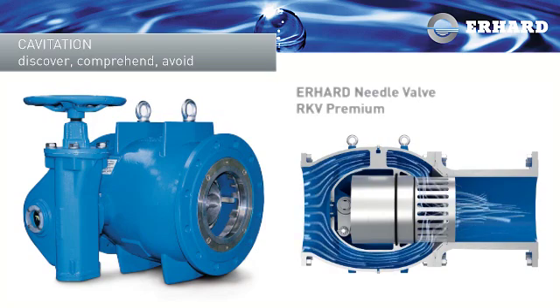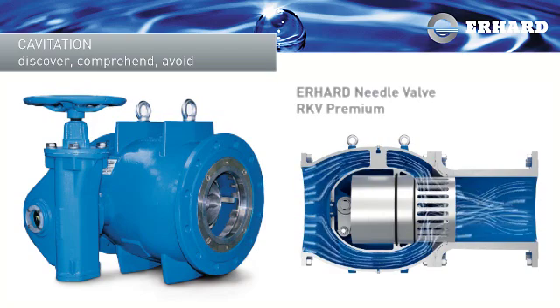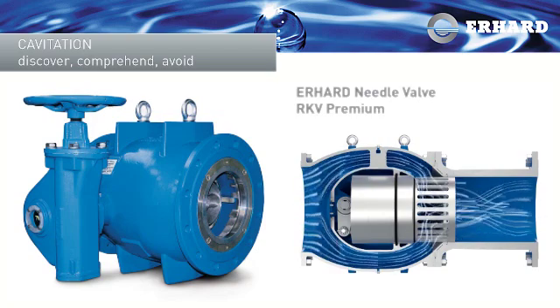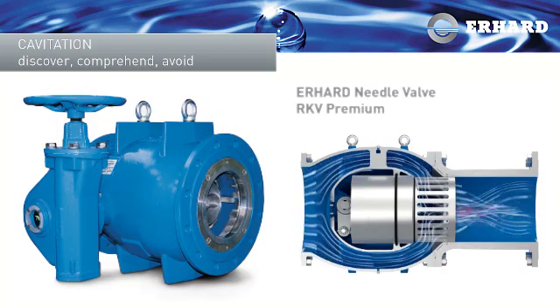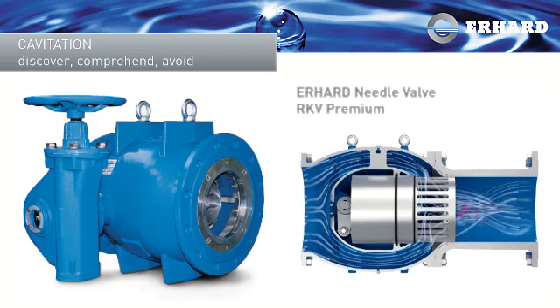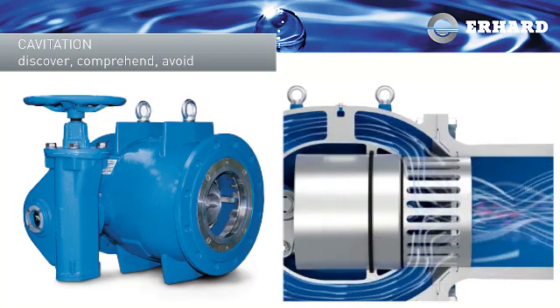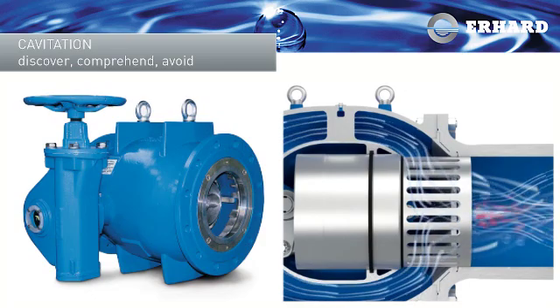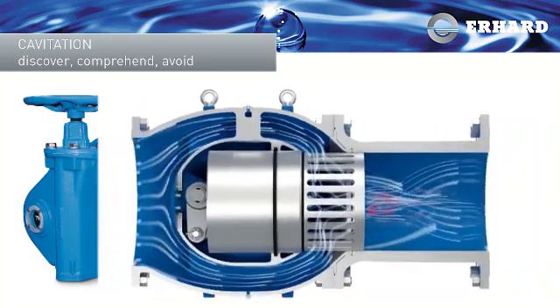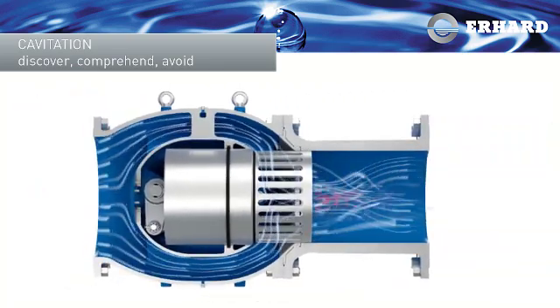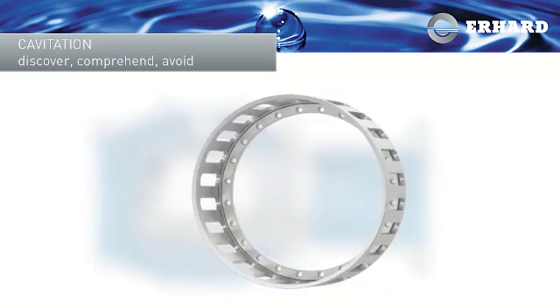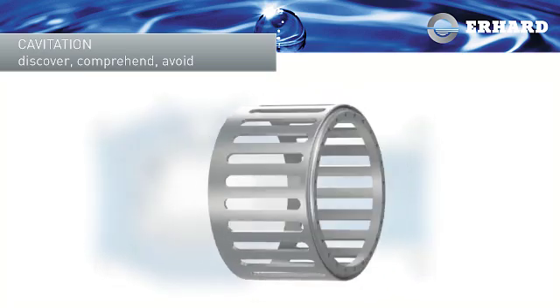Pure physics makes cavitation unavoidable even in these, but suitable measures reduce it or make it harmless. Special control inserts, for example, ensure that instead of at the body wall, the cavitation takes place in the centre of the pipe. It doesn't cause any harm there.